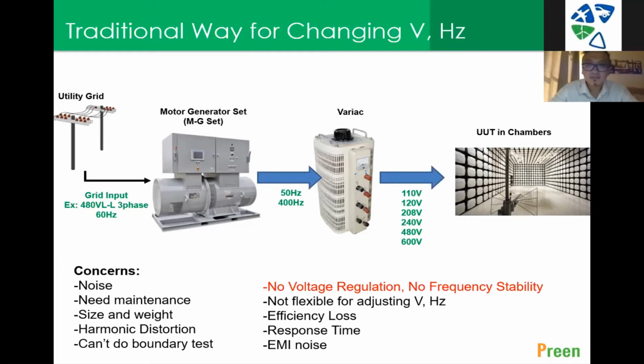When the grid voltage has noise, the variable transformer will pass the noise to your testing unit as well. So if there is a lot of harmonic noise here, you will see a lot of harmonic noise here. The other thing is that when the grid voltage drops, like the original is 480 but it drops to 470, your output, originally 110, will drop as well, to 105. So there is no frequency stability or voltage regulation on this one. When you start some load, you cannot control your voltage well.